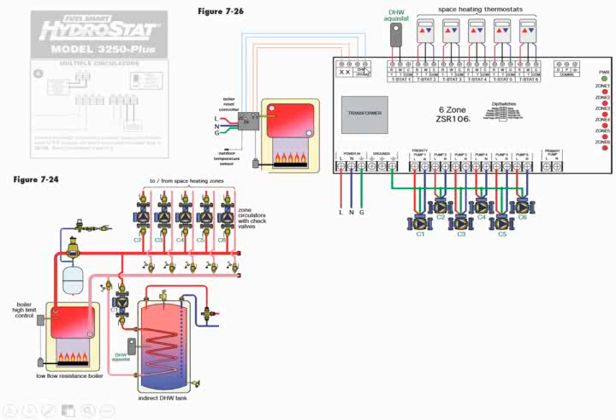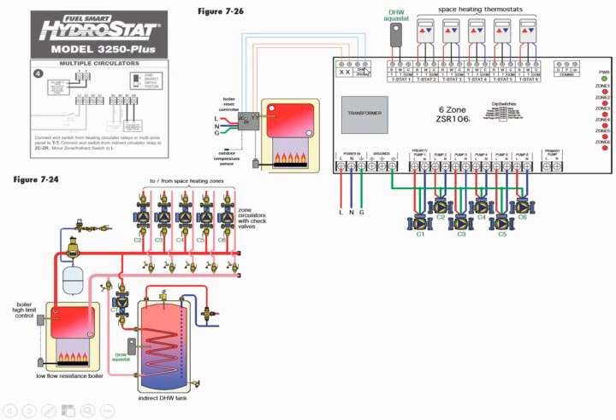Okay, here's a sample schematic. Again, this is out of Hydronic. You can see the figures up here. What we've got is a conventional boiler with a bunch of zone pumps and a domestic hot water priority pump. So our wiring on this is we're tying XX to TT on the boiler control. And this has a reset control, so we'd have ZR and ZC over to our domestic hot water contacts over here. An example of that is like the hydrostat. They're 3250 plus. They even show ZR, ZC going to an end switch, so that can do it for you.